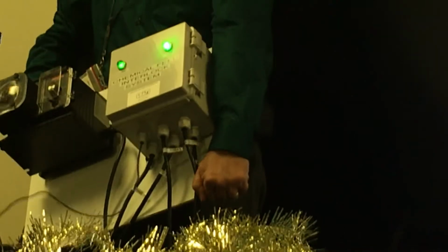So if I were to do this, and power terminates, it goes off. Circuit breaker went off, somebody flipped the switch, nothing can work. And that's all based on a flow switch. Your flow switch would go in line in your main line, in your main recirculation. No side stream. No flow, no feed. So with the feeder, you can do the flow control. So this is the best method of interlocking chemical feeders and chemical controllers.